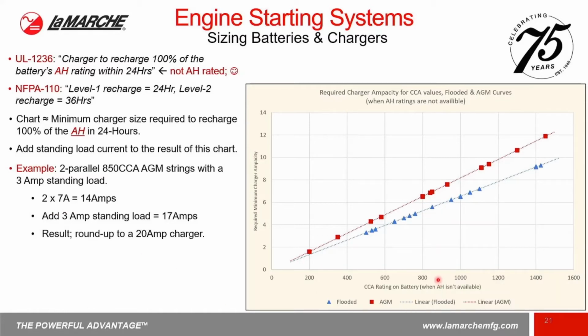So let's go through an example. Let's say I want 2 parallel 850 cold cranking amp AGM battery strings that has a 3 amp standing load. I would first look up 850 amps, that's right over here. That gets me to a 7 amp charger. So I've got 2 of them, so I need a 14 amp charger. Then I have to add my 3 amp standing load, so we get 17 amps. Well, we don't have a 17 amp charger available, so we round up to 20 amps.